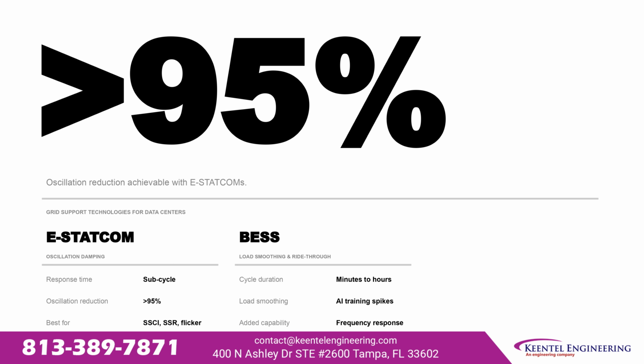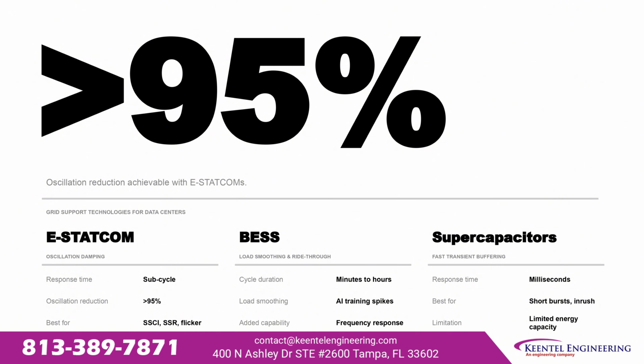BESS for load smoothing and ride-through. Minutes to hours of cycle duration, smooths AI training spikes and adds frequency response capability on top. And supercapacitors for fast transient buffering, millisecond response, best for short bursts and inrush events. Energy capacity is the limitation. Each technology targets a different timescale. The right solution depends on which study area is driving the requirement.